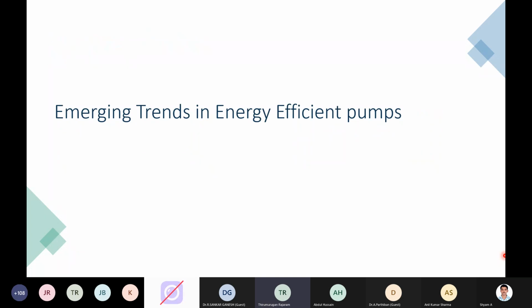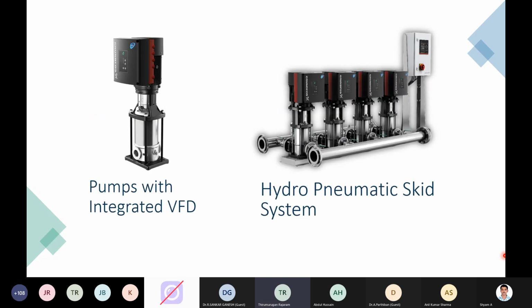So now we touch upon the emerging trends in energy efficient pumps. You have already seen the integrated VFD approach in the market, where instead of having a separate control panel for the VFD, we can have pumps with integrated VFDs and a controller, pre-programmed for the pumping application. I can program the pump for pressure, temperature, or level applications. Even parallel operated skids can come as a plug and play solution for variable demand applications.